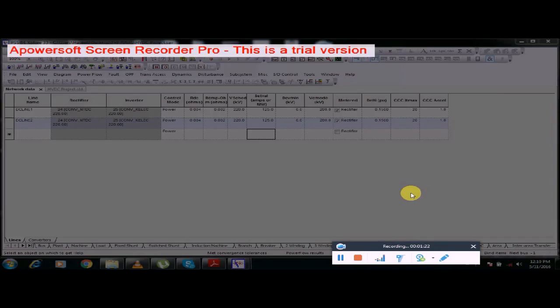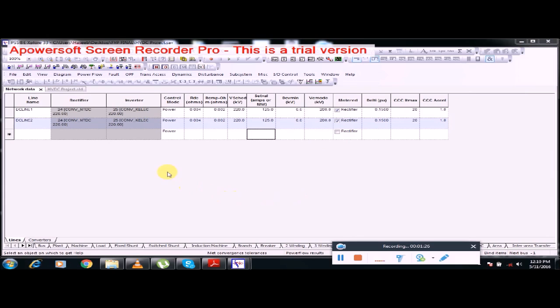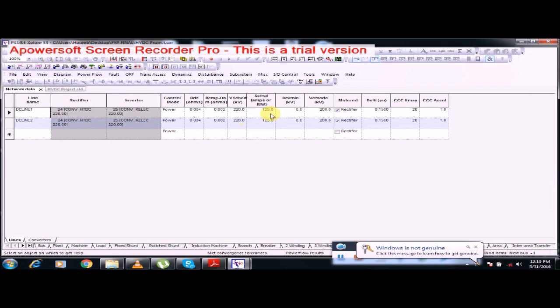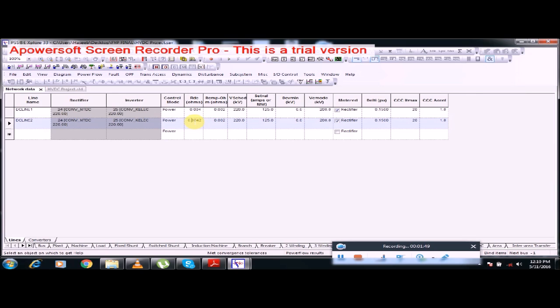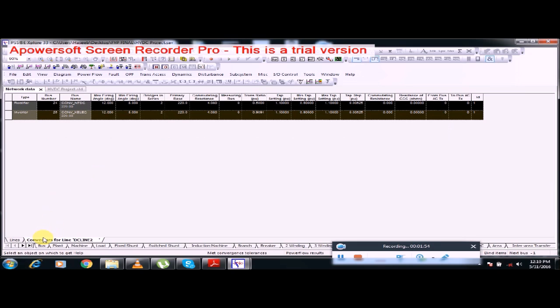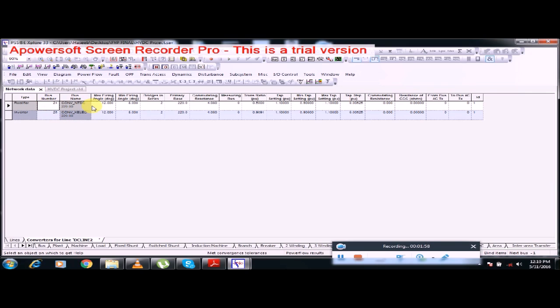The design parameters of our HVDC back-to-back link are: rated power of 250 megawatts, firing angle range of 8 to 12 degrees, DC resistance of 0.04 ohms, selected buses of NKI1, NKI2-Baldia, and NKI2-KDA, tap range of 0.9 to 1.1, and operating voltage of 220 kilovolts. In the PSSE file, there are two DC lines each carrying an HVDC converter station — the first carrying 125 megawatts and likewise the second. The rectifier and inverter parameters, including maximum and minimum firing angles, primary base voltage of 220 kilovolts, and DC line resistance, have all been entered according to the design.